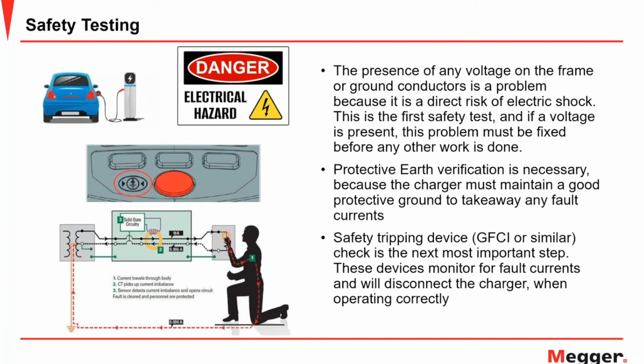If there is a fault current in the charge point, but there's no voltage present because there's a good protective earth, then there'll be a flow of earth leakage current through that protective earth. And if the tripping device is not functioning or is not installed properly, then even though there's this higher current flowing through the protective earth, it's not tripping, it's not disconnecting, and raising the flag that there's an issue here.